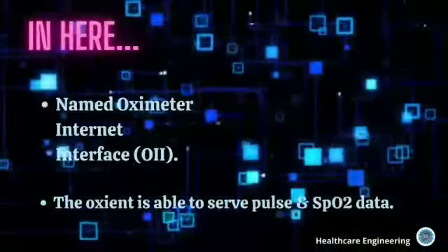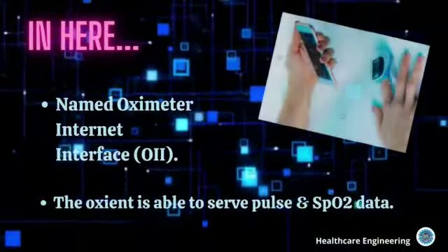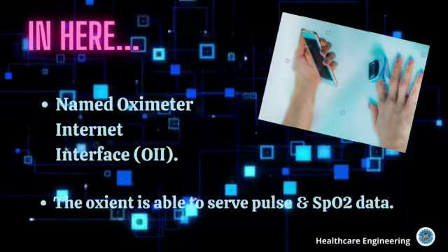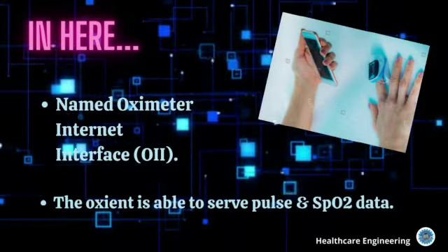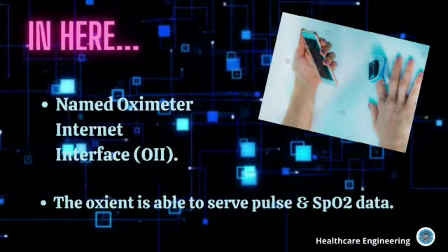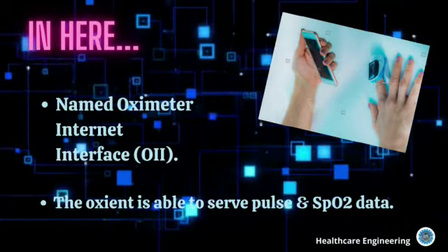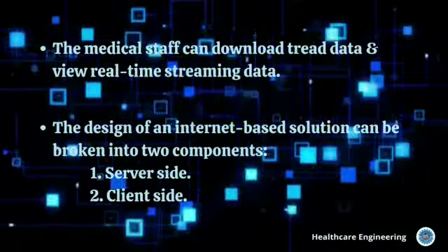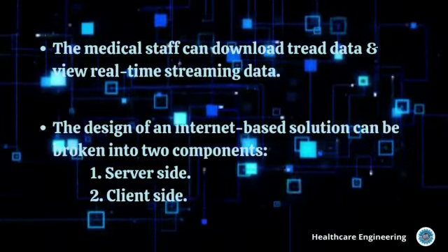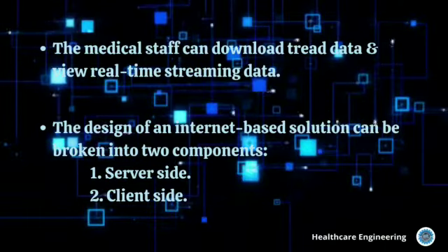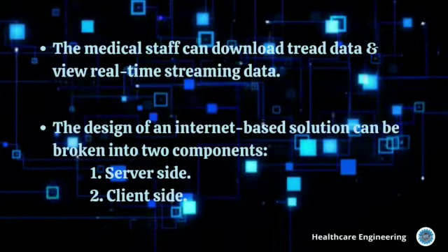The proposed system, named Oximeter Internet Interface or OII, is a web server connected via a serial interface to a pulse oximeter. The Oxinet is able to serve pulse and SpO2 data as well as trend information to the internet. The medical staff can download trend data and view real-time streaming data from any web browser. This is accomplished through the language of the internet, HTML and Java applets.